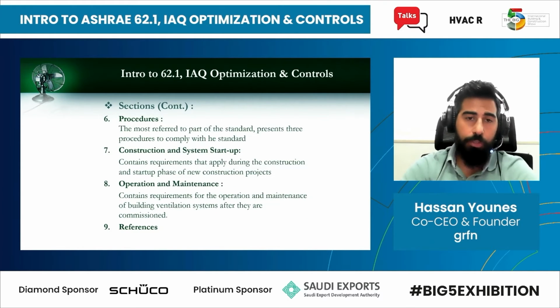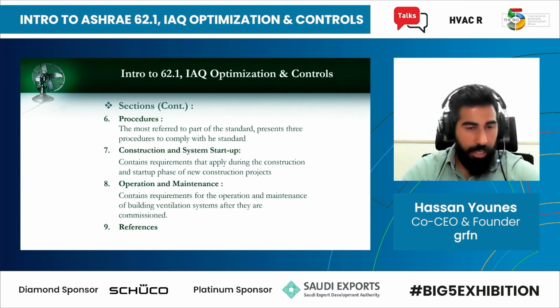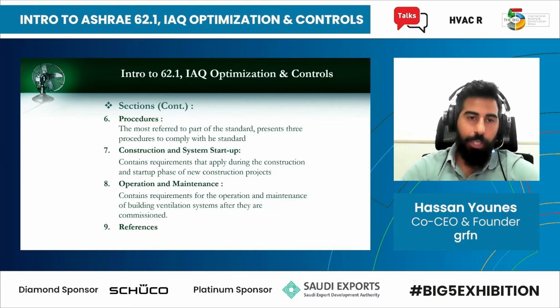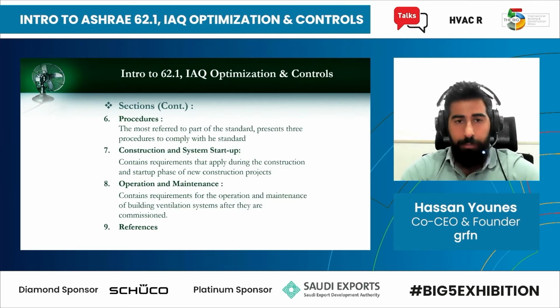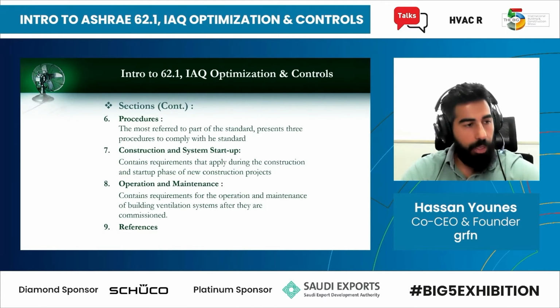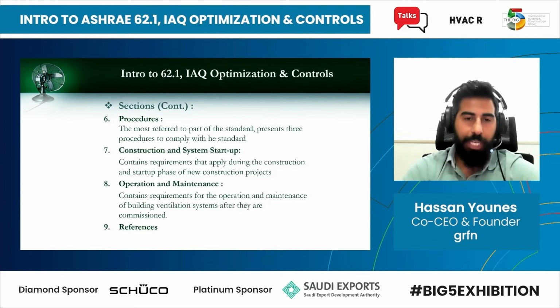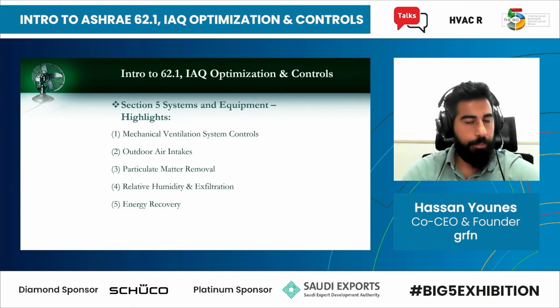Then it goes into procedures, which is the main part that consultants would normally look at, especially the ventilation rate procedure. Then there's a section on construction, system startup, operation and maintenance, and then some references. But in general, you would need to look at all the sections to be able to comply with the standard. You can't just look at section 6 and say, I am complying with the standard because I'm delivering the quantities as per Table 6, in terms of the requirement of outside air per person or per area. You need to look at all the different sections, check the requirements and apply them.